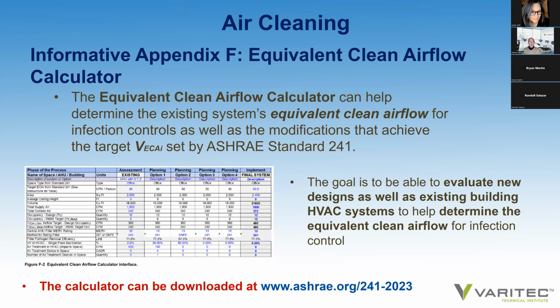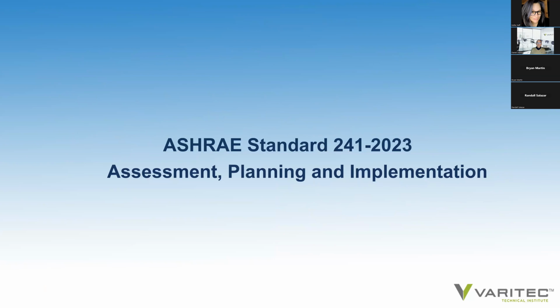Now, if you think that in order to design a building and to determine the total amount of equivalent clean airflow rates that each zone requires depending on air cleaning technologies, I could put your mind at ease and let you know that the standard offers, under informative Appendix F, an equivalent clean airflow calculator. It will allow you to enter all the variables of the various zones, and it will determine the amount of clean airflow that will need to be delivered. And then the question is which technologies can you rely on to give you validated and tested credible performance data to meet them.